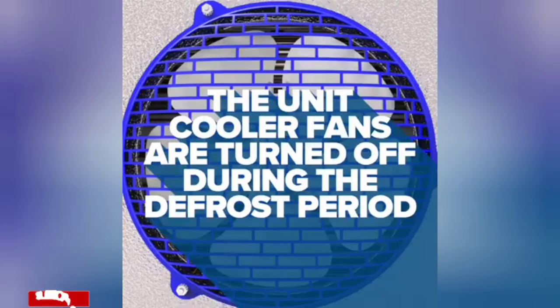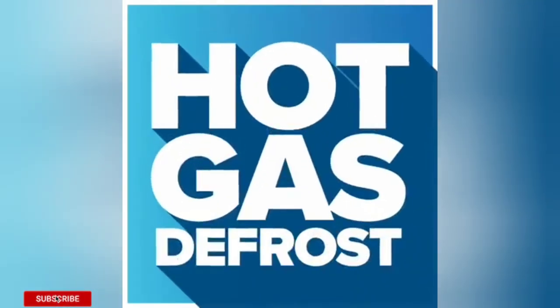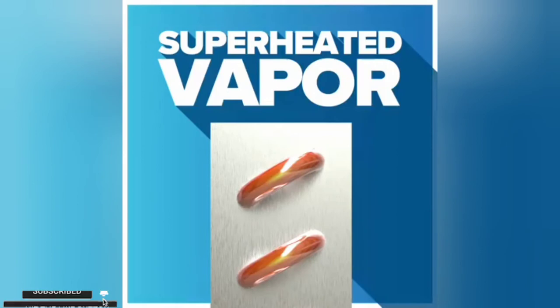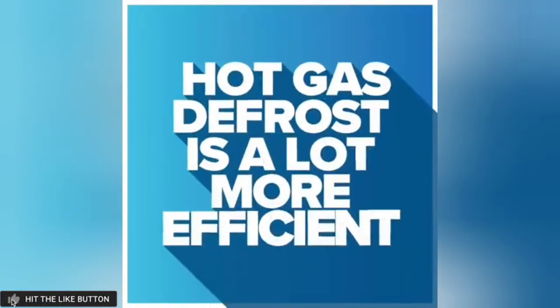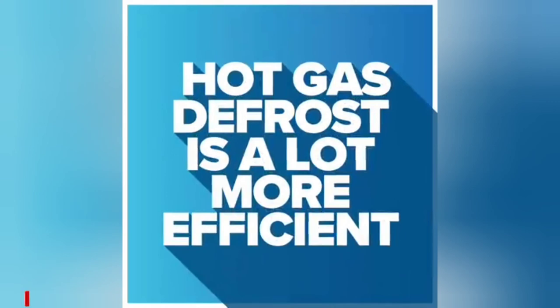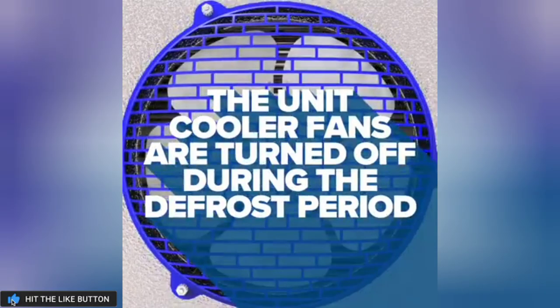Last is the hot gas defrost system, which uses the superheated vapor from the compressor discharge port to warm the evaporator coil to melt the ice. While not as widely applied as electric defrost, hot gas defrost is a lot more efficient, since the heat source flows through the coil circuit allowing more effective heat exchange with the formed ice. During this type of defrost, the evaporator fans are turned off for the defrost period.